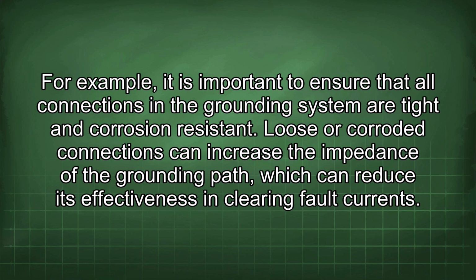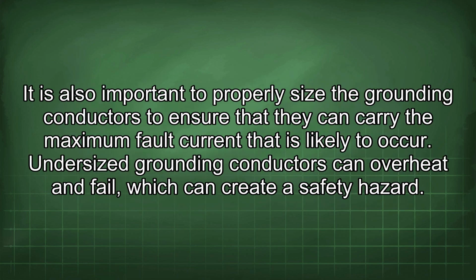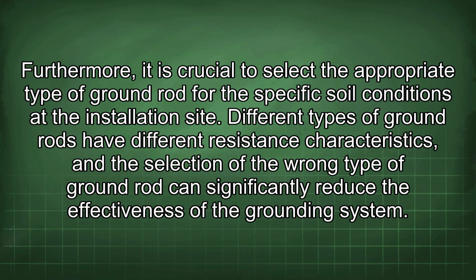For example, it is important to ensure that all connections in the grounding system are tight and corrosion resistant. Loose or corroded connections can increase the impedance of the grounding path, which can reduce its effectiveness in clearing fault currents. It is also important to properly size the grounding conductors to ensure that they can carry the maximum fault current that is likely to occur. Undersized grounding conductors can overheat and fail, which can create a safety hazard. Furthermore, it is crucial to select the appropriate type of ground rod for the specific soil conditions at the installation site. Different types of ground rods have different resistance characteristics, and the selection of the wrong type of ground rod can significantly reduce the effectiveness of the grounding system.